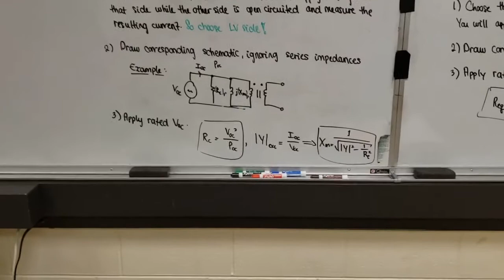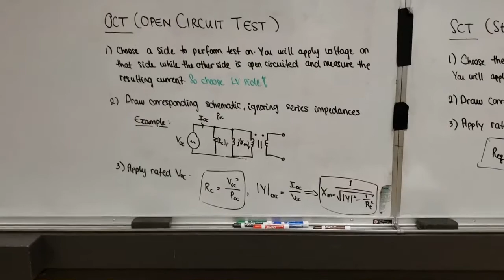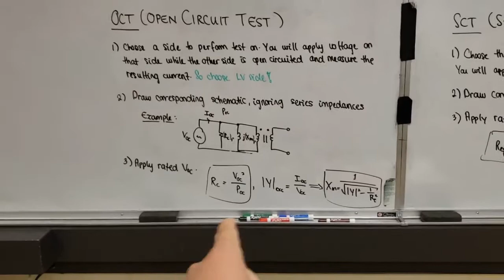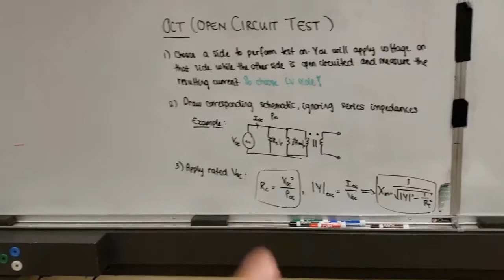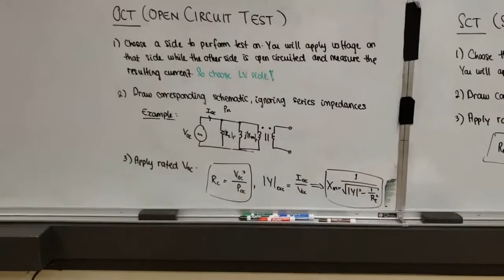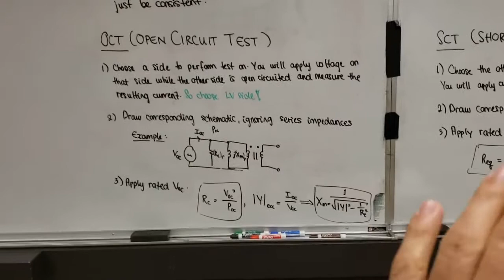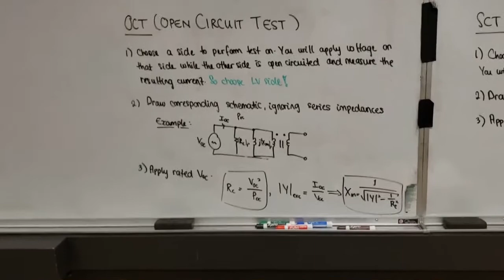I wrote that the copper losses are the magnitude of the current squared, I squared R losses. I'll be careful: R equivalent is referred to one particular side. So if you're looking at the primary side, R equivalent, then that I squared is that primary side current. If everything was referred to the secondary, then you use the secondary side current squared times R equivalent on the secondary. Using these, you can characterize a bunch of things, and we're going to see that in the lab today as well. This is important in characterizing your transformer.